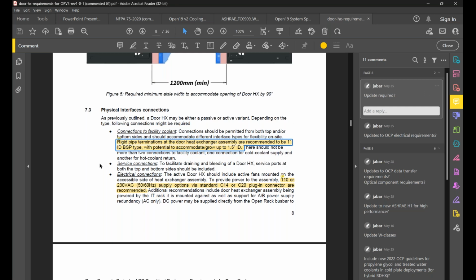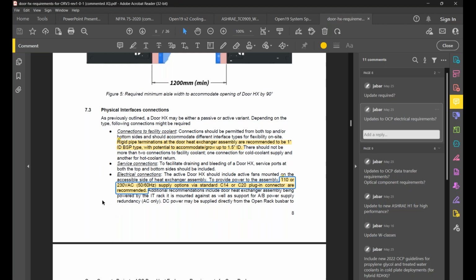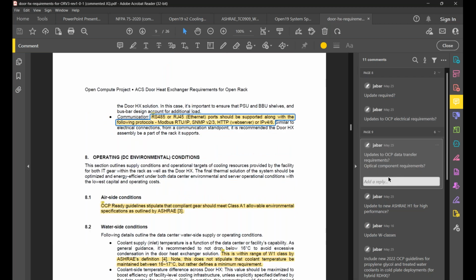So I was wondering if this physical interface connection requirement here, for it to be 1-inch ID BSP type, has been updated, based on what people would have done in other parts of OCP and the kind of flows expected in terms of facility coolant, if we're still using 1-inch as the standard. Also in terms of the electrical requirements and connector types, if that was updated in another part of OCP on hardware management, I'm not sure. Same thing with the data connections, if these are still the standard connections you're using, or if they've also been updated. So those are the 3 categories in terms of cooling, data, and power that need to be checked to make sure we're referencing things that still exist.